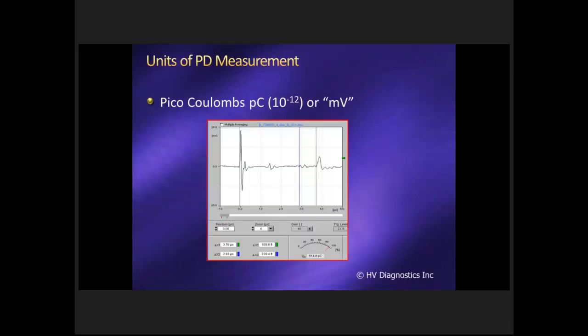So if we look at the units of PD, typically they are either in millivolts or in picocoulombs or nanocoulombs. Coulomb is the measurement. And as you can see over here, we have the PD impulse, and I don't know if you can see the mouse here, but the incident impulse over here has a PD amplitude of 540 picocoulombs, and the millivolt signal, you can get an idea of how small PD impulses are compared to the applied voltage. Very, very minute discharges that take place.